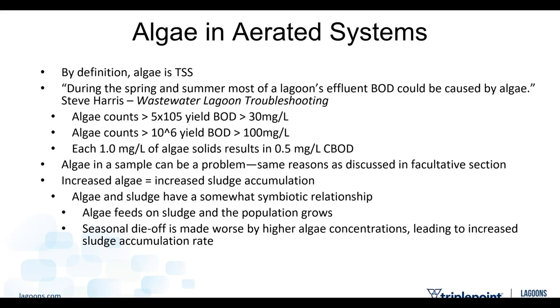Flipping over and looking at algae in an aerated system. By definition, algae in an aerated system is total suspended solids. And I love this quote here from Steve: during the spring and summer, most of the lagoon's effluent BOD could be caused by algae. We saw that on that fact sheet a couple of minutes ago, 94 out of 100 milligrams per liter in that example coming from algae. And you've got some counts and yields that you see in terms of a concentration in milligrams per liter. Each milligram per liter of algae solids is going to result in about a half a milligram per liter of CBOD, carbonaceous biochemical oxygen demand.